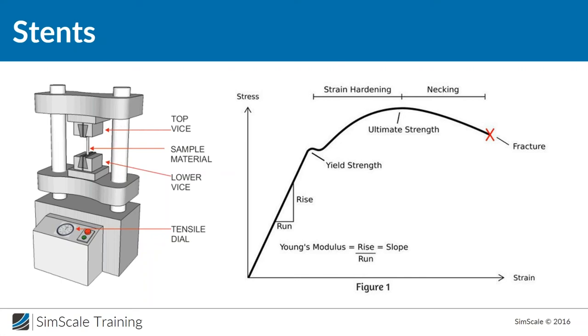Anwar also asked if the force is really uniform through the whole process of stent inflation — and for sure it is not. This is just a simplification, because in reality we have three-dimensional stress states in a three-dimensional device. I hope this example still helps you understand the main challenge when designing a stent.